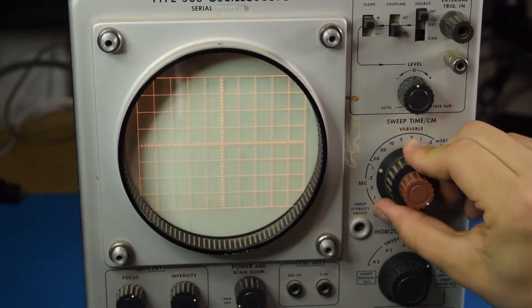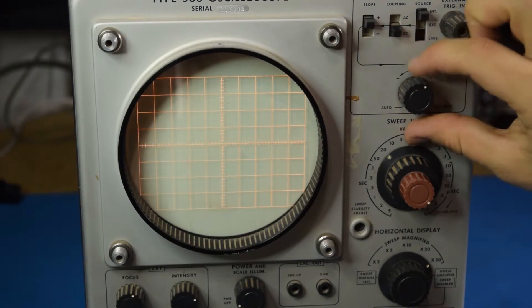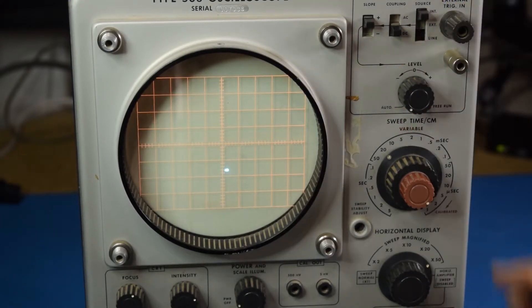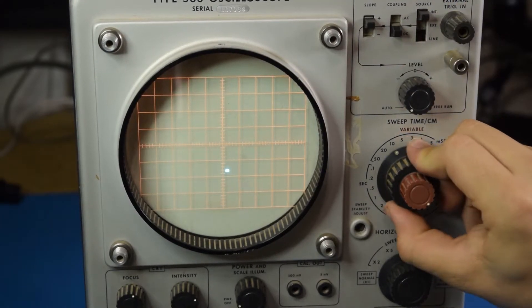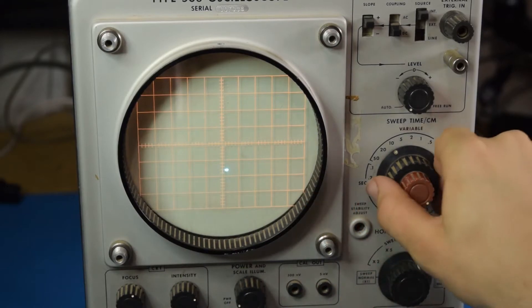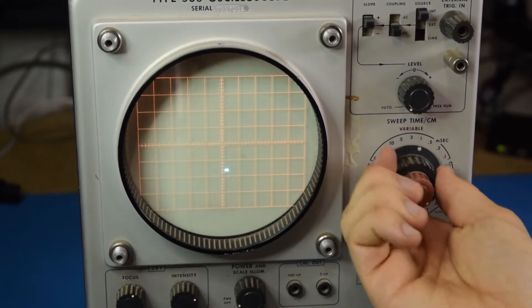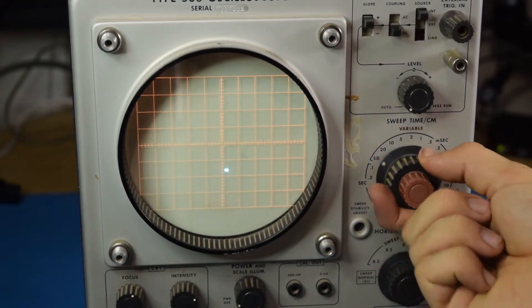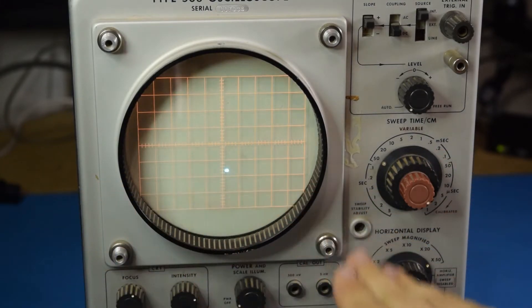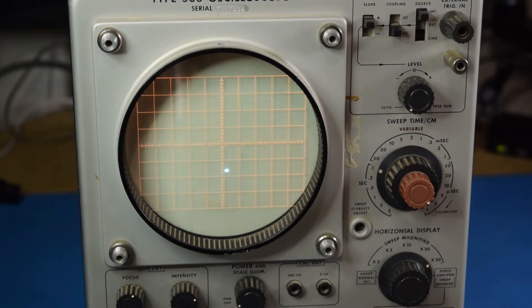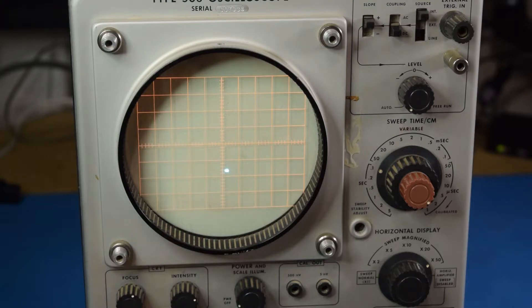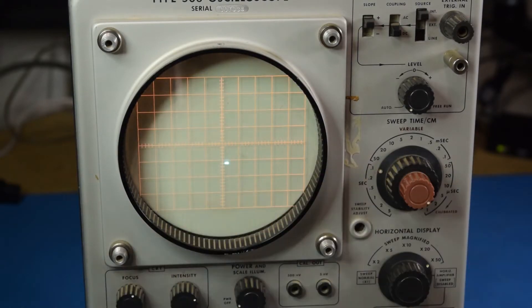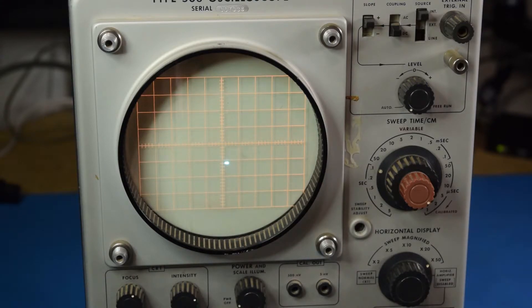Now, that dot that keeps disappearing should be moving across the screen. As I adjust the sweep time, it's changing how long it would take for it to scan across, but it's stopped in one position. I can move it up and down the vertical axis, which should be voltage, but even that doesn't respond when I apply a voltage to the input.